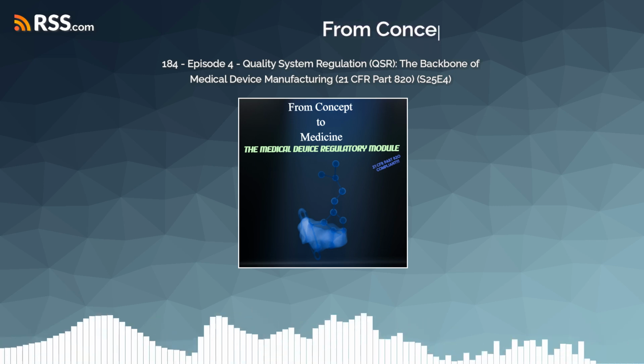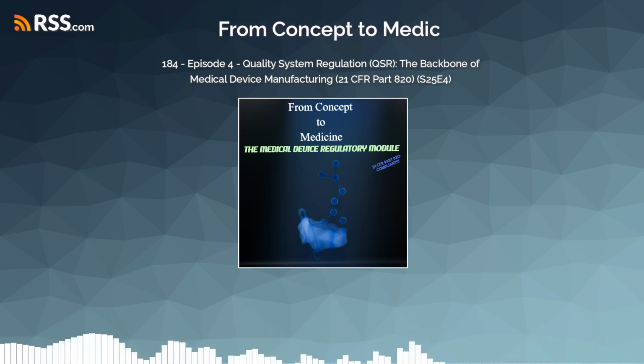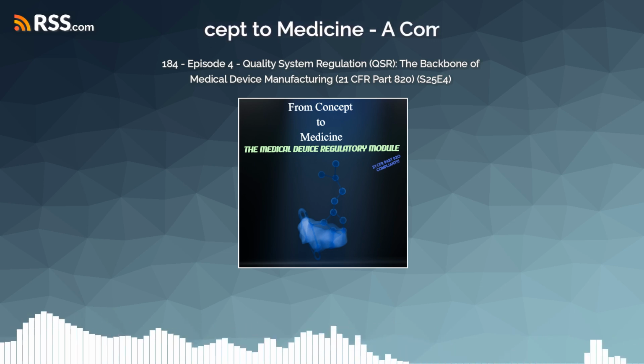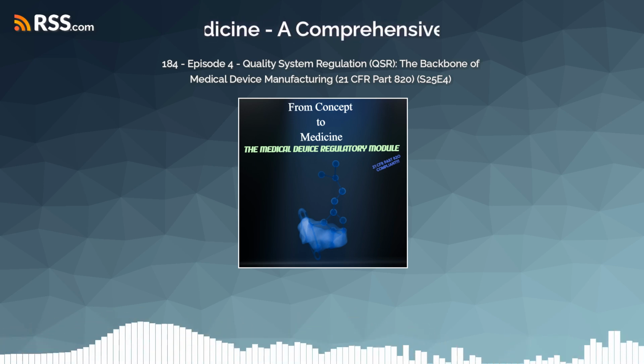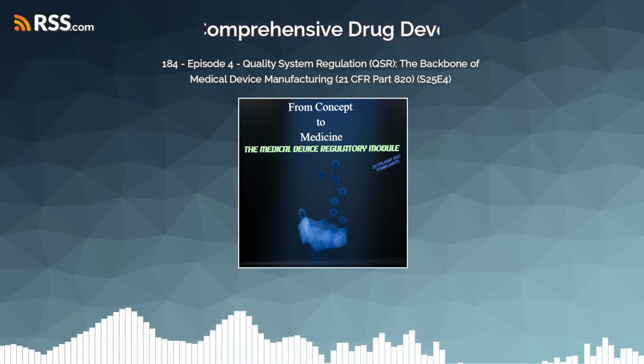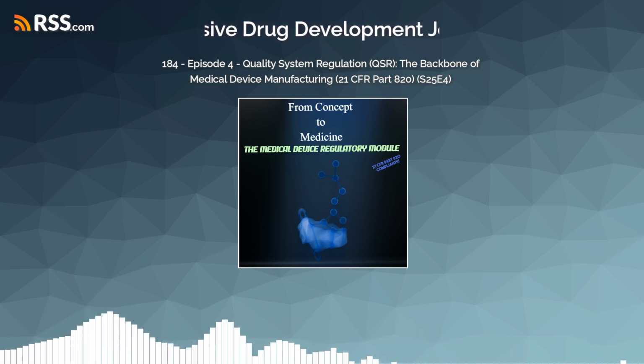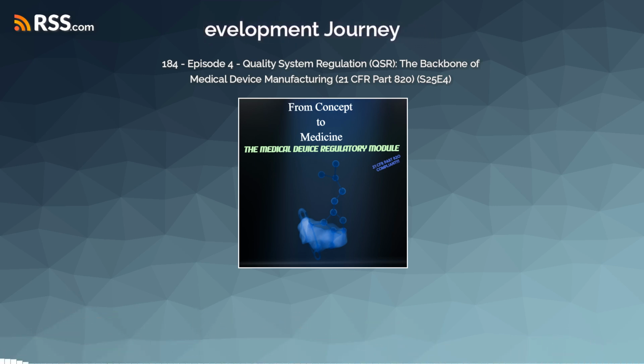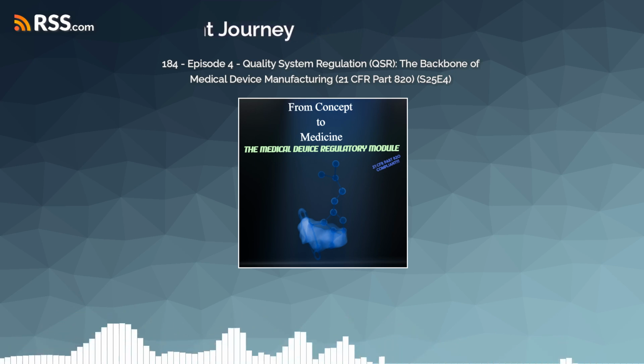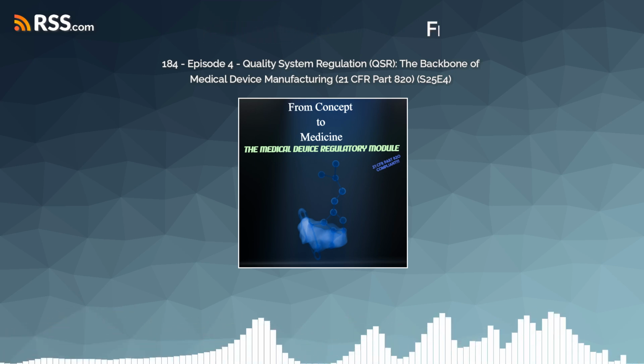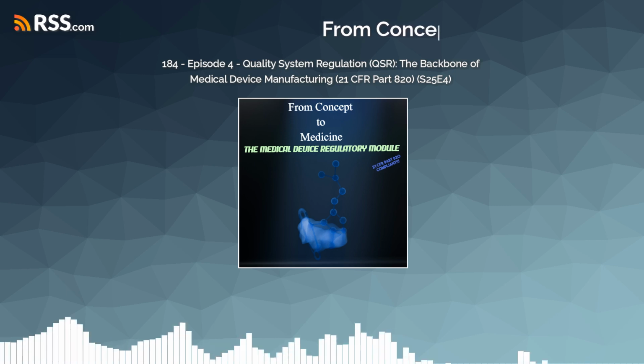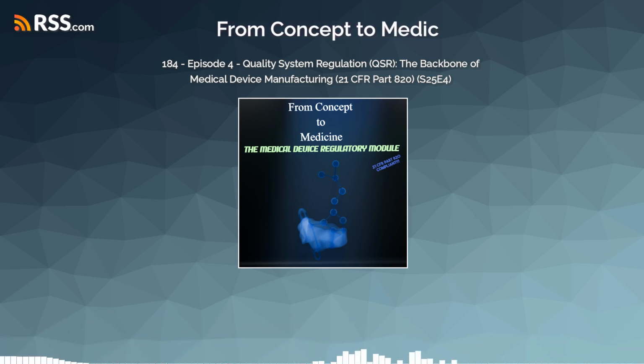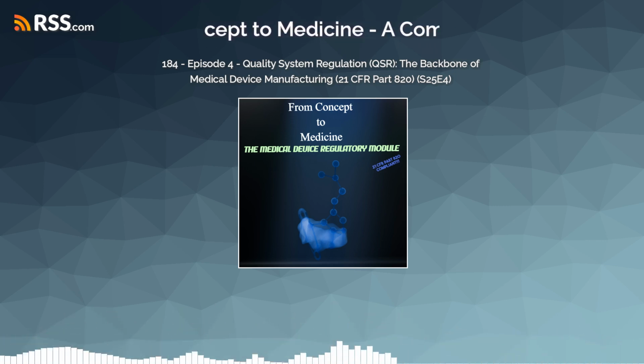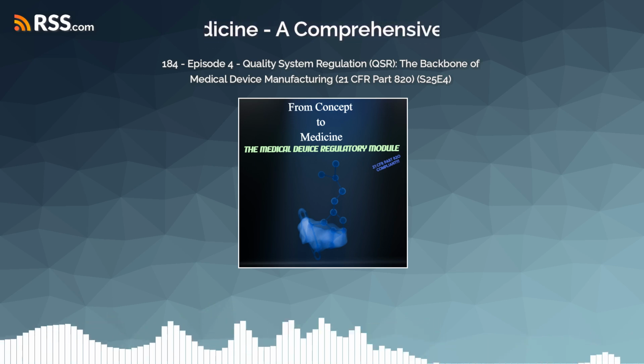You know, I remember a case where a company had great PQ results on paper, looked perfect. But they hadn't fully accounted for the ambient humidity fluctuations in the actual production suite during different times of the year. It threw off one sensitive measurement just enough. So the real world intruded. Yes. It's a reminder that qualification has to reflect actual operating reality, not just ideal lab conditions.